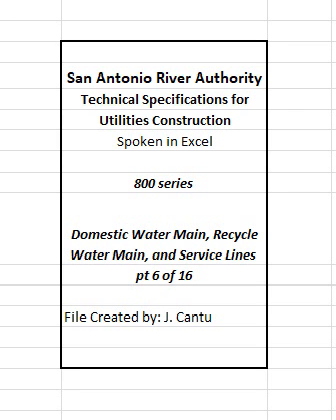2. Pipe joint restraint system for HDPE pipe. Restraint devices shall be used where ductile iron mechanical joint bell fittings are coupled to plain end, square cut, HDPE pipe, to prevent movement of pipe connections. The restraint system shall have a minimum pressure rating of 250 psi. The restrainer must not be directionally sensitive.